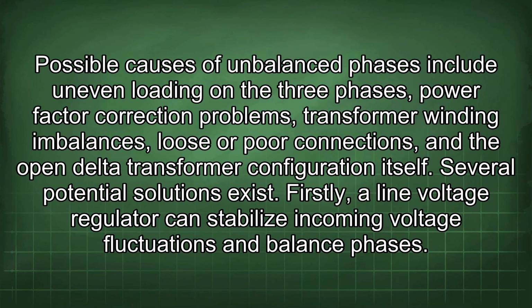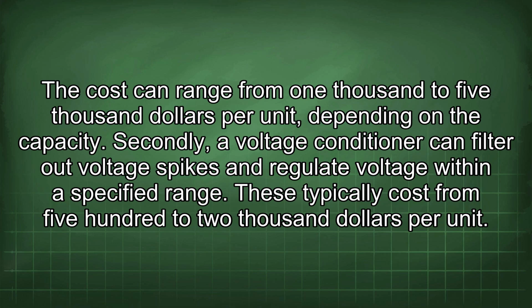Possible causes of unbalanced phases include uneven loading on the three phases, power factor correction problems, transformer winding imbalances, loose or poor connections, and the open delta transformer configuration itself. Several potential solutions exist. Firstly, a line voltage regulator can stabilize incoming voltage fluctuations and balance phases. The cost can range from $1,000 to $5,000 per unit, depending on the capacity.